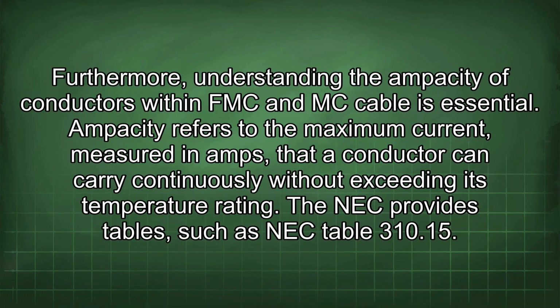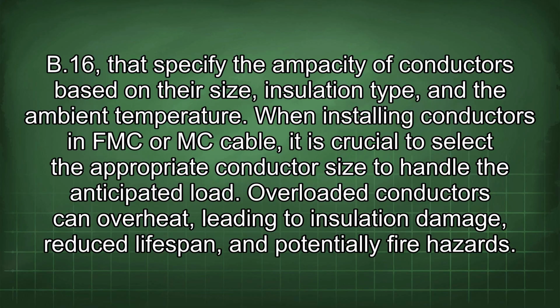Furthermore, understanding the ampacity of conductors within FMC and MC cable is essential. Ampacity refers to the maximum current, measured in amps, that a conductor can carry continuously without exceeding its temperature rating. The NEC provides tables, such as NEC Table 310.15(B)(16), that specify the ampacity of conductors based on their size, insulation type, and the ambient temperature. When installing conductors in FMC or MC cable, it is crucial to select the appropriate conductor size to handle the anticipated load. Overloaded conductors can overheat, leading to insulation damage, reduced lifespan, and potentially fire hazards.